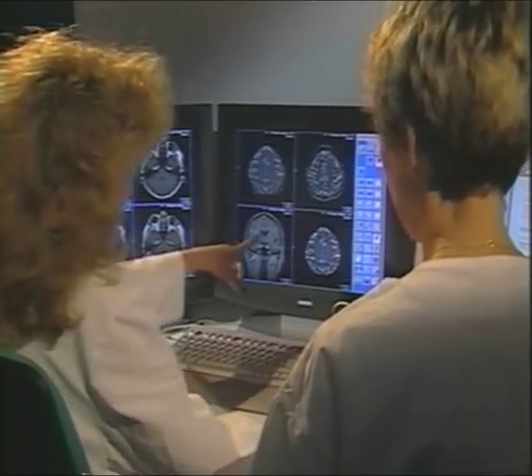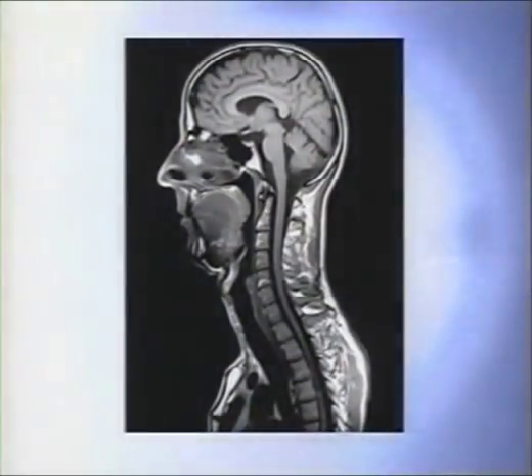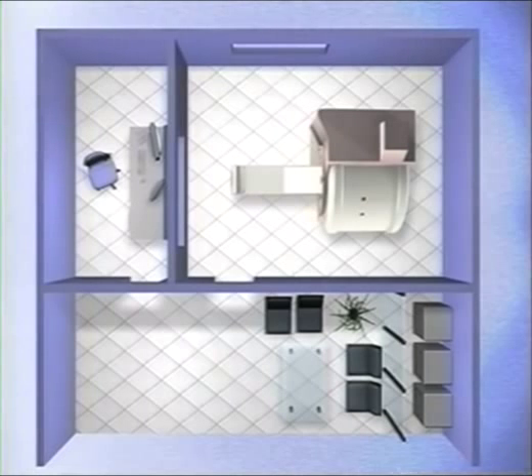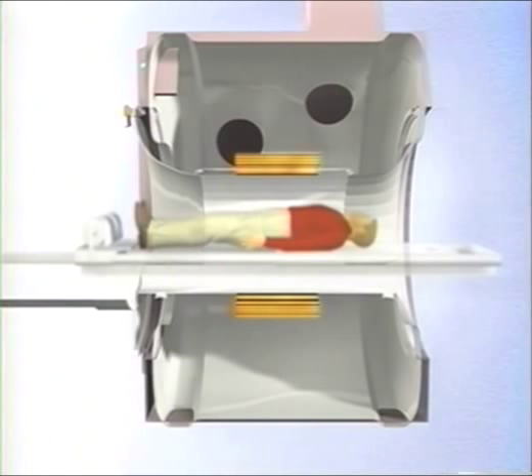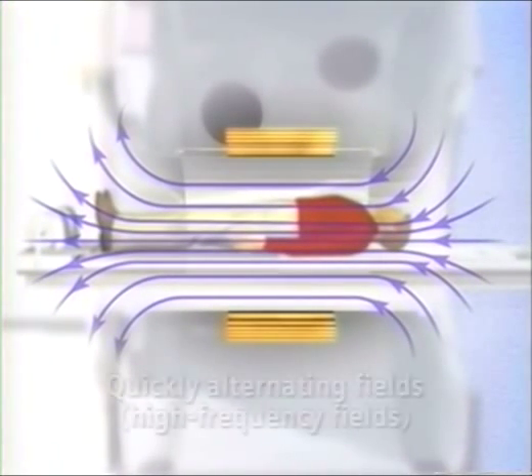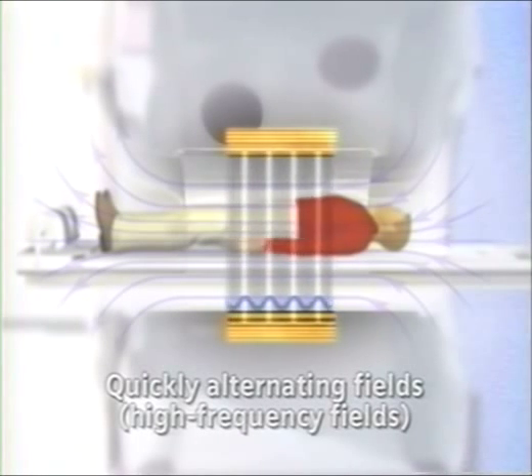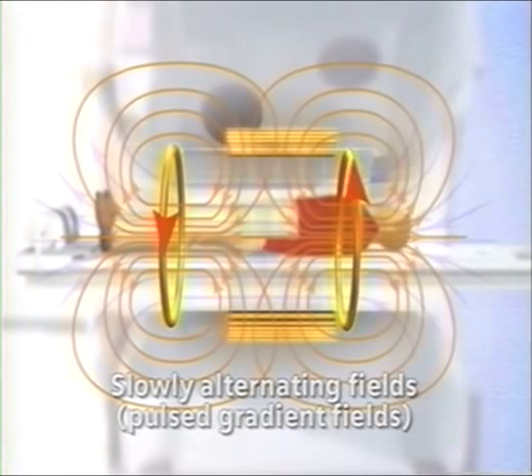A computer program analyzes the MR signals and generates an image of the distribution of the hydrogen atomic nuclei in the human body. The MR unit is housed in an RF enclosure. This ensures that the very weak signals from the RF pulses are not contaminated with interference and cannot cause radio interference outside the enclosure. Therefore, the patient is exposed to three different magnetic fields during the MR examination: the static main magnetic field that aligns the atomic nuclei; the high-frequency alternating field that disrupts the alignment; and the pulsed gradient field that enables correlation of the MR signals to the location of origination.